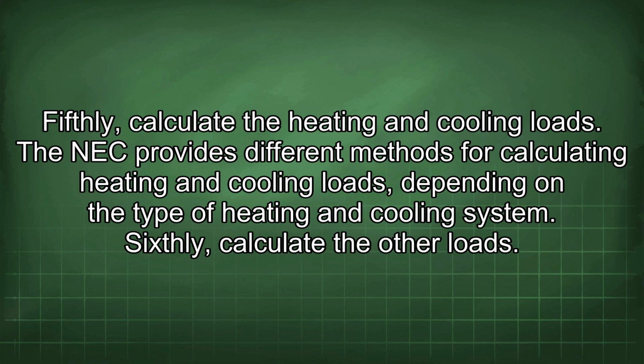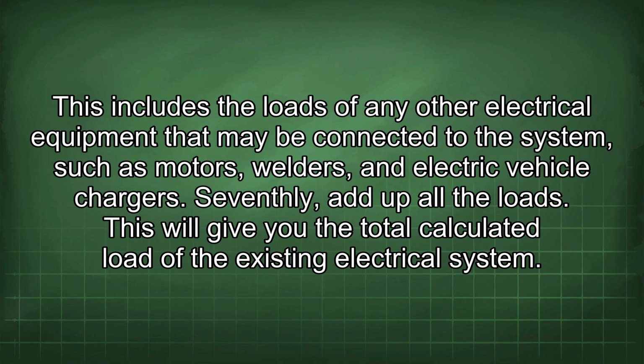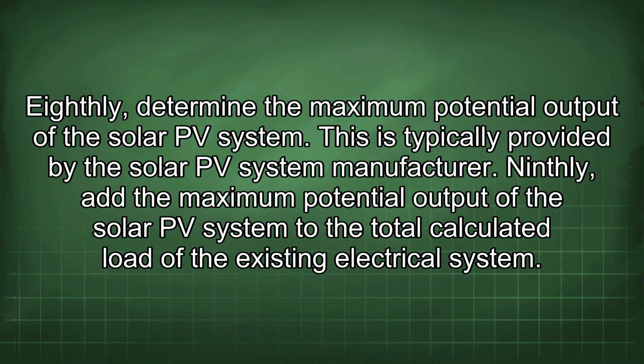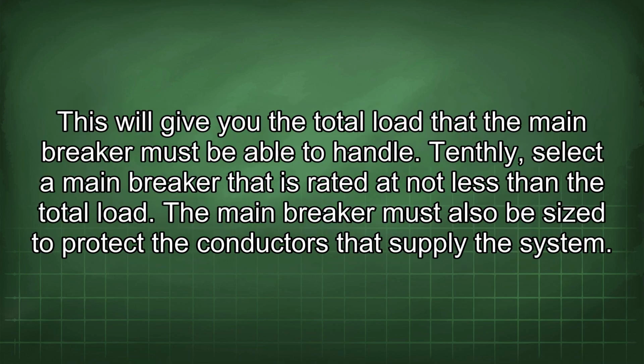Sixthly, calculate the other loads. This includes the loads of any other electrical equipment that may be connected to the system, such as motors, welders, and electric vehicle chargers. Seventhly, add up all the loads. This will give you the total calculated load of the existing electrical system. Eighthly, determine the maximum potential output of the solar PV system. This is typically provided by the solar PV system manufacturer. Ninthly, add the maximum potential output of the solar PV system to the total calculated load of the existing electrical system. This will give you the total load that the main breaker must be able to handle. Tenthly, select a main breaker that is rated at not less than the total load. The main breaker must also be sized to protect the conductors that supply the system.